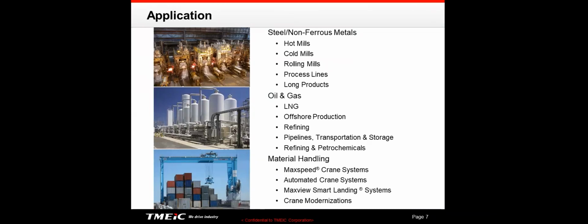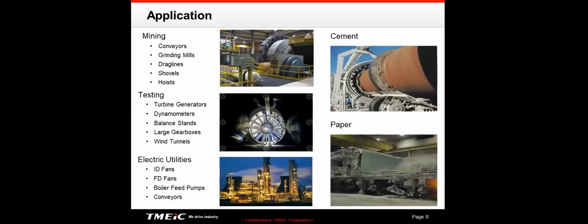So when you look at drives manufacturers, it used to be there were only a few medium voltage drives manufacturers. Now it seems like everybody's getting into the business. But most of the medium voltage drives manufacturers go towards the fans, pumps, and compressors and just really produce standalone drives. And it's a smaller subset of people who produce the systems drives that are able to produce full systems, like in steel mills, paper mills, material handling, and things of that sort.